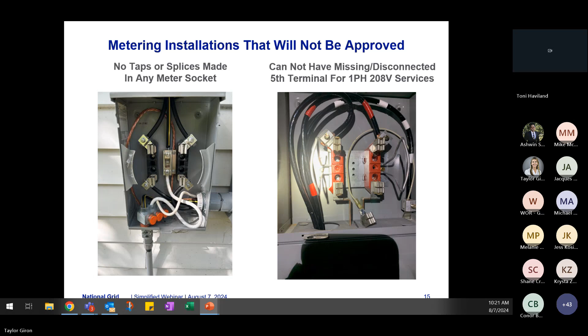National Grid has a lot of older infrastructure areas, like some Beverly areas, Malden, Worcester, where we have single phase 208 volt services. We've had some issues where projects got delayed because the wrong style meter socket was installed, like a single phase 120/240 volt meter socket, because the voltage wasn't measured properly at the site. These are rare, but they do come up, and we would love to ensure that you're installing the right equipment for the right voltage on site.